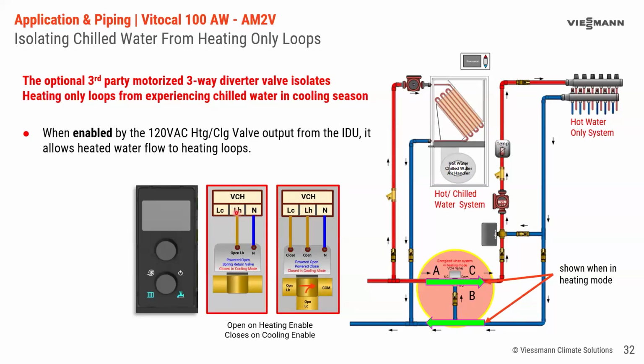So that's why over here we're going to say in a two-way valve, we're going to power the valve open. In a three-way valve, we're going to bypass water this way and not let the water go this way. And I'm showing you in this drawing a two-way valve and a three-way valve. Either one of these could be powered open, powered closed, or powered open spring return. I was just trying to declutter the drawing a bit.